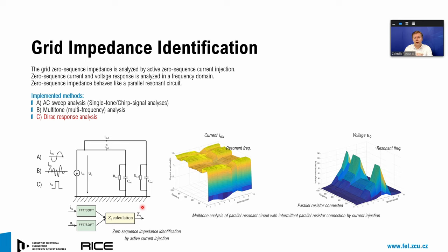Nevertheless, we have one big benefit. We have a current source installed in the system. Our power electronics converter is able to generate a testing signal by which we are able to identify the grid impedance in real time. We implemented two possible techniques, multi-frequency analysis, and we have the best experience with the pseudo-Dirac response analysis. It means that we inject into the grid a pseudo-Dirac impulse. We know the current impulse, we know its frequency composition, and we measure the voltage response of the grid. We do the frequency analysis, and based on it, we can calculate the grid impedance in real time. And it makes it possible to calculate the necessary compensation current, which we are generating by our device.